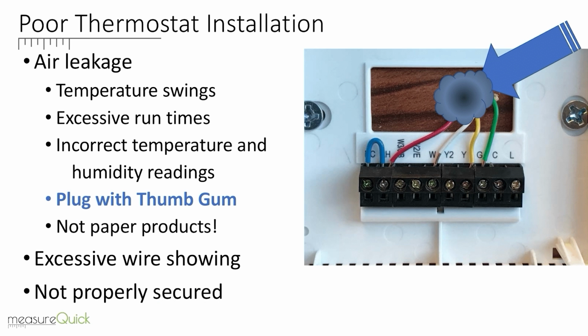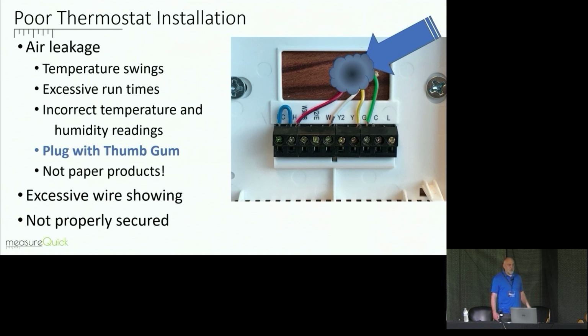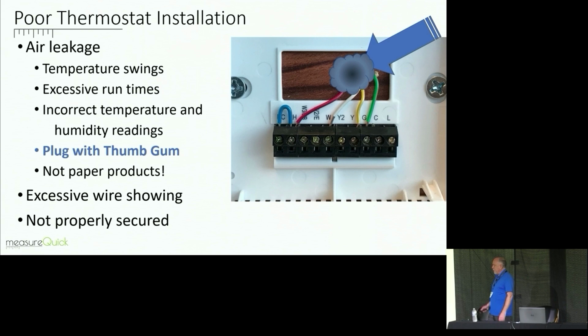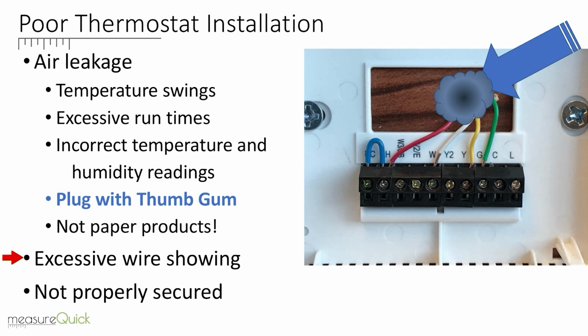And that's even more important today that we plug this hole up with some thumb gum, because we have incorrect humidity readings on the thermostat also. A lot of humidity readings are incorrect because we're pushing, again, water vapor up through there. So you want to make sure when you're doing that, you're not using paper products. Also, obviously, you can see we got excessive wire showing here, not properly secured, right?